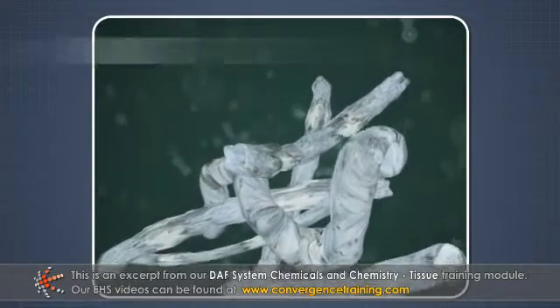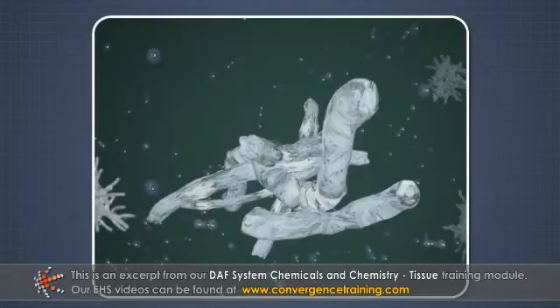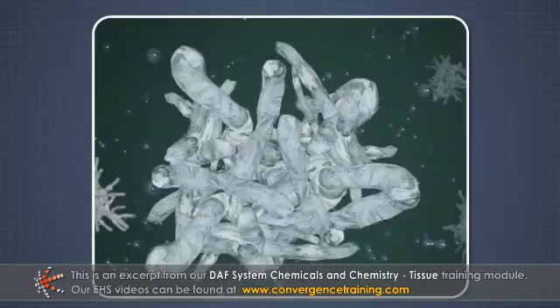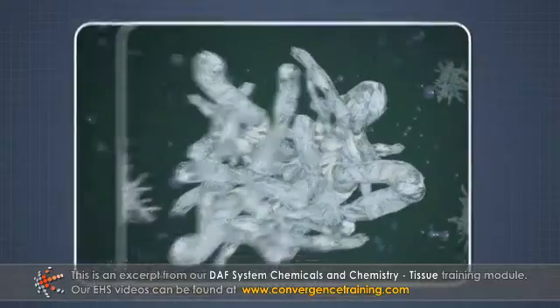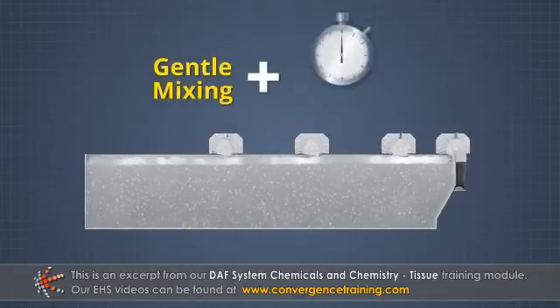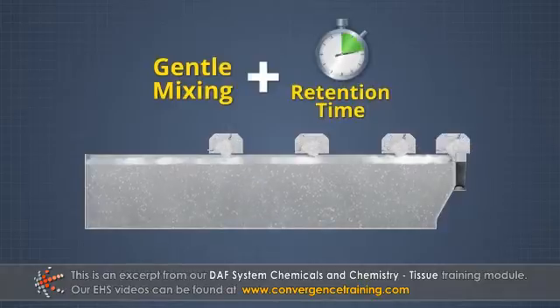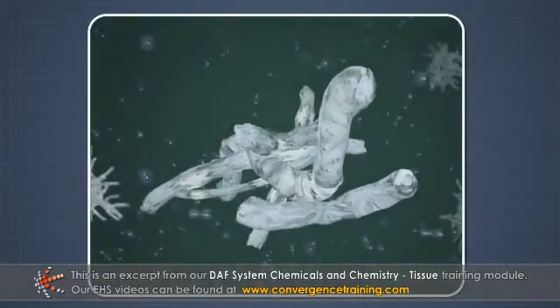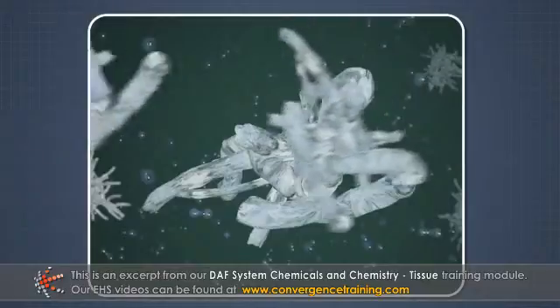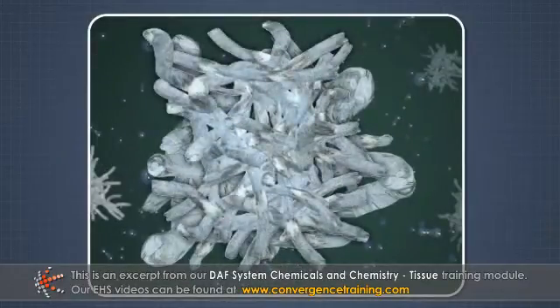The process of bringing the microfloc formed by coagulation together into even larger aggregates or floc is called flocculation. The flocculation process follows the coagulation process, and it requires gentle mixing and sufficient retention time to allow the large floc to form. During flocculation, the floc size of the particle aggregates continues to build and grow through additional particle collisions and interactions with added synthetic polymers.